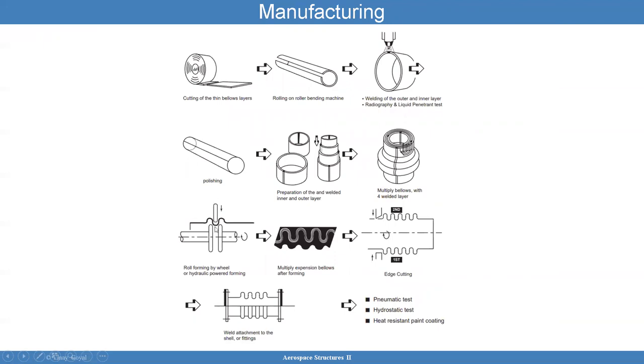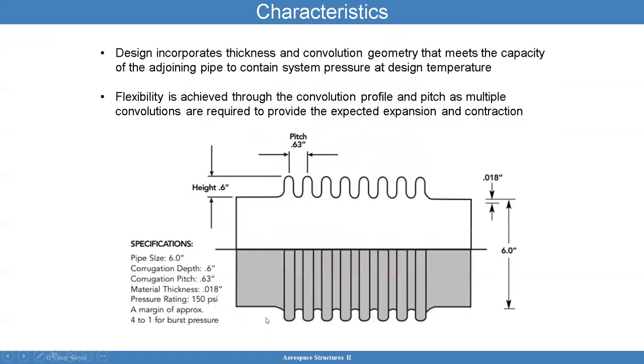You stack them in there and then form them. After forming them with a die — here you have a hydraulic powered forming process — you can see multiple plies through the thickness. Then you attach the ends. The design incorporates thickness and convolution geometry that meets the capacity of adjoining pipe to contain system pressure. For example, the pitch is 0.63, the height is 0.6, and the material thickness is 0.018 with a six-inch diameter. This particular design has a 4-to-1 burst pressure — meaning if it operates at 100 psi, it was designed to take 400 psi.